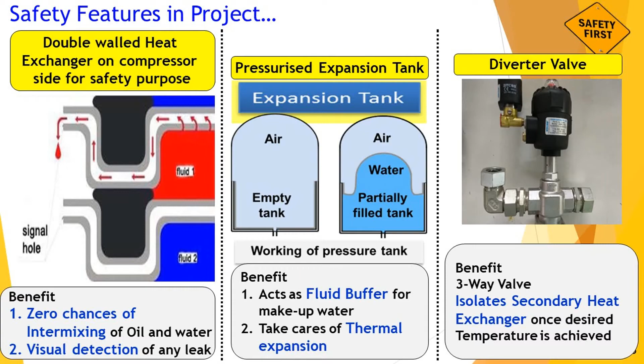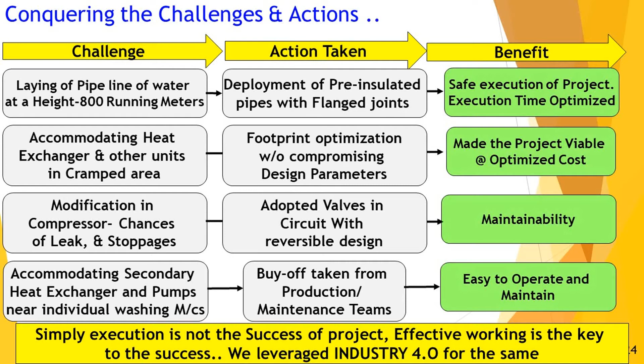Other challenges were laying of the pipeline, 100 meters, 800 meters at a height. So we got pre-insulated pipes with flange end and bolted together. So this optimized the time for execution. For accommodating the heat exchanger, we have a multi-pass, plate type heat exchanger, thereby we were able to reduce the footprint of the heat exchanger. Similarly, we have incorporated valves and other NRVs so as to make this design reversible for ease of maintainability and operability. Simply execution of this project is not the success of the project.